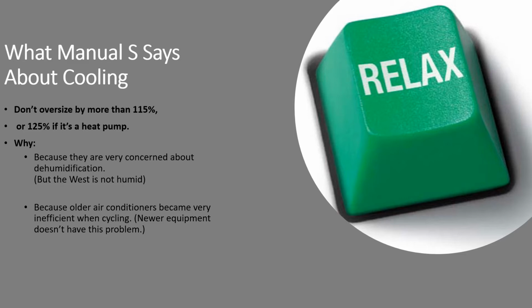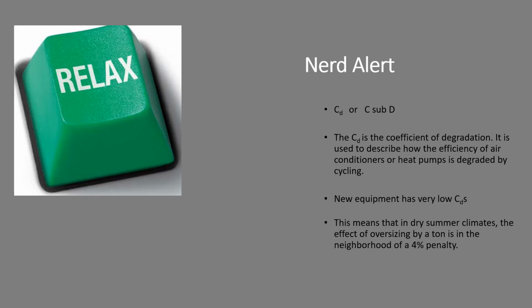Also, older air conditioners had a big penalty for not having long cycles. Newer equipment has improved significantly. The penalty for cycling is something called the C sub D, or the coefficient of degradation. It's used to describe how the efficiency of an air conditioner or heat pump is degraded by cycling. It used to be C sub Ds would hit you with maybe a 25 or 30% penalty if it cycled. The new ones are much lower than that.